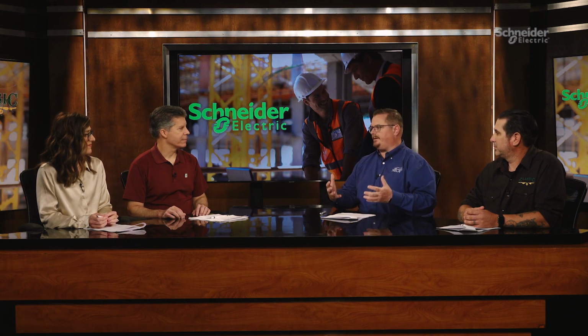You know, for a long time, it's always just been you need emergency system backup or legally required system backup, you installed a generator. Now new requirements in the NEC, or new permissive requirements in the NEC, allow you to use energy storage systems for those systems in addition to or supplementing a backup generator. Yeah, and that alleviates a lot of concern, right? It uses the clean source first and can reduce how much diesel fuel you have to store on site, which is also a concern for aging and keeping that fuel and system ready to run.